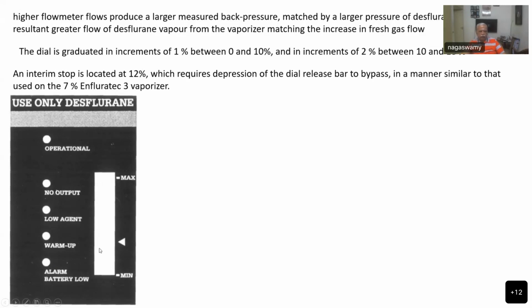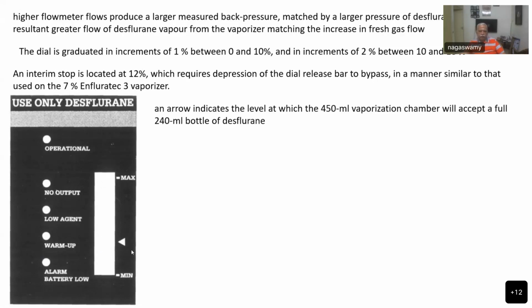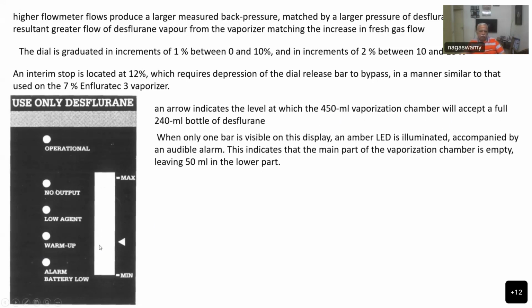And you have a sighting glass to see the level from minimum to maximum, and an arrow here indicates 450 ml vaporization chamber, accept a full 240 ml bottle of desflurane, and only one bar. And when it is operational, instead of the level of fluid, you will see the bars indicate the amount of liquid that is left in. So when one bar is in display, an amber LED light is illuminated, accompanied by an audible alarm. This indicates that the main part of the vaporization chamber is empty, leaving only 50 ml in the lower part.